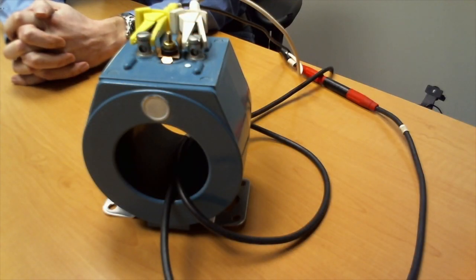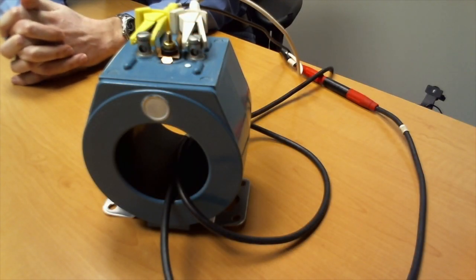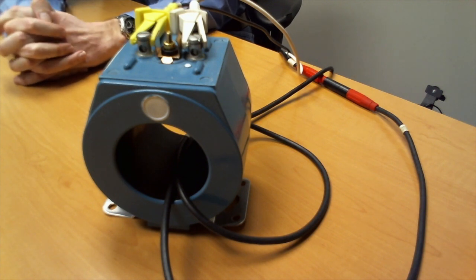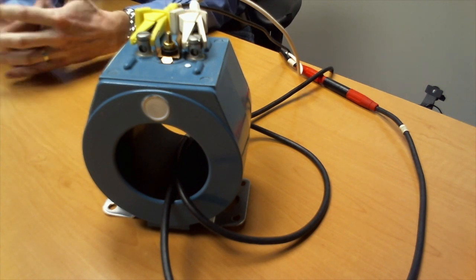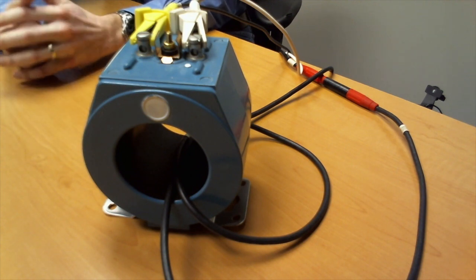I think they're the most fascinating component of the metering system. Meters read what they read, but with transformers, there are so many variables you can move, with rating factor, thermal rating, and accuracy class, that I can maximize my investment, let's say, to get the most I need out of that installation.